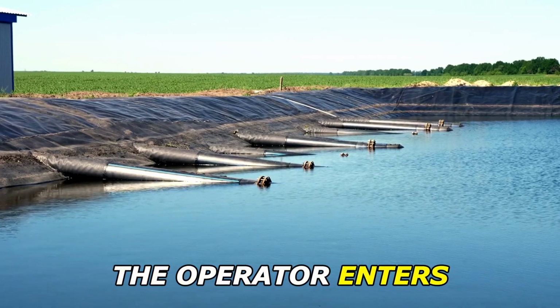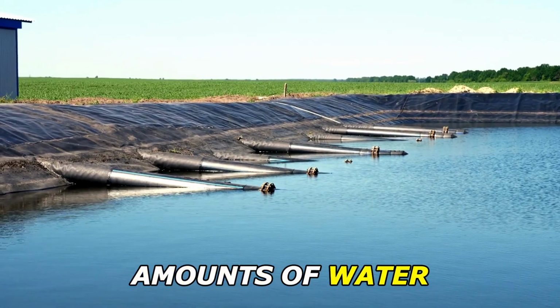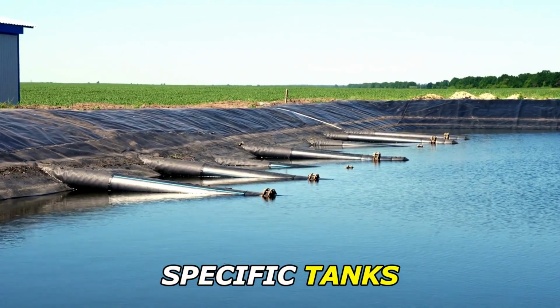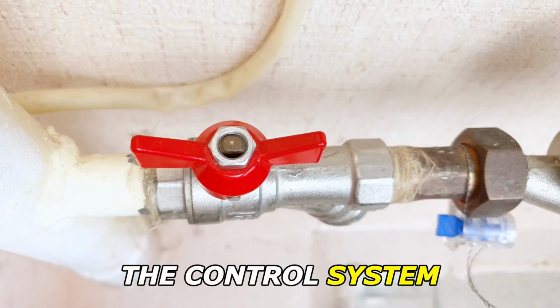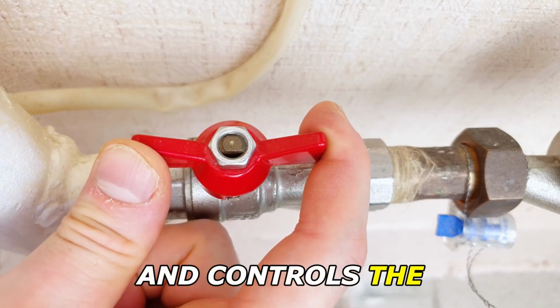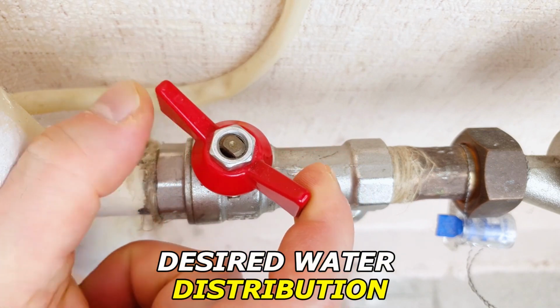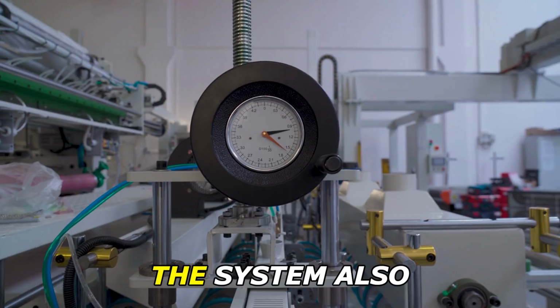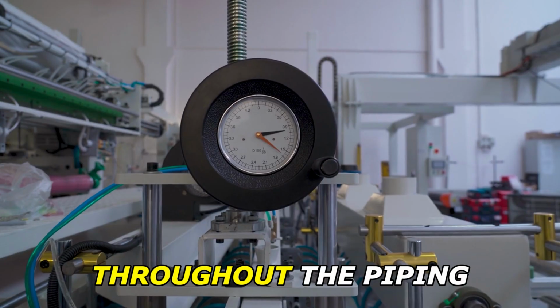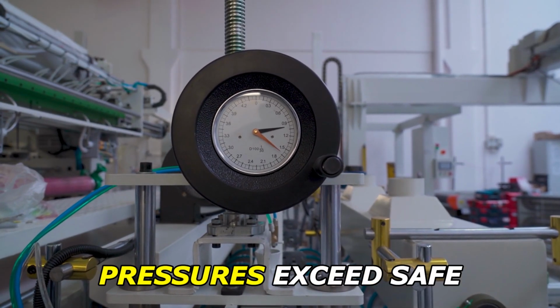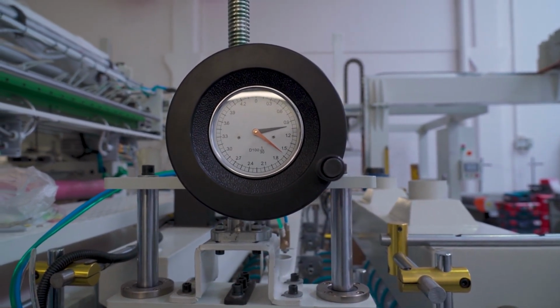The operator enters commands to pump specific amounts of water into or out of specific tanks. The control system activates the pump and controls the valves to achieve the desired water distribution. The system also monitors pressures throughout the piping system and alarms if pressures exceed safe limits.